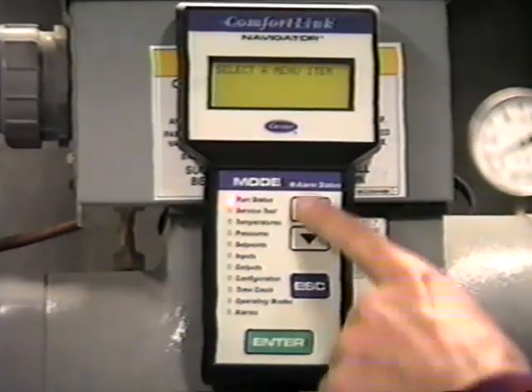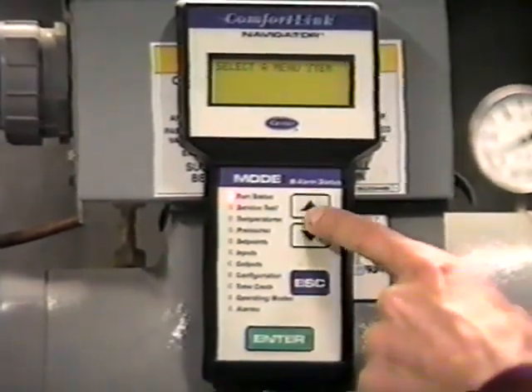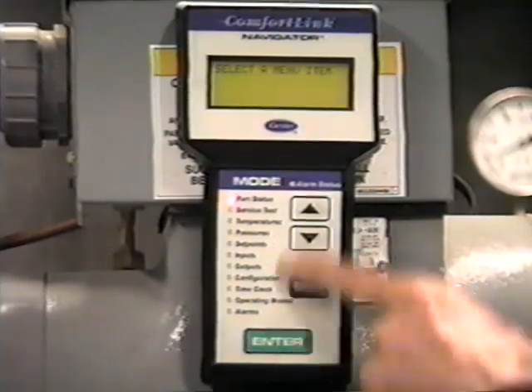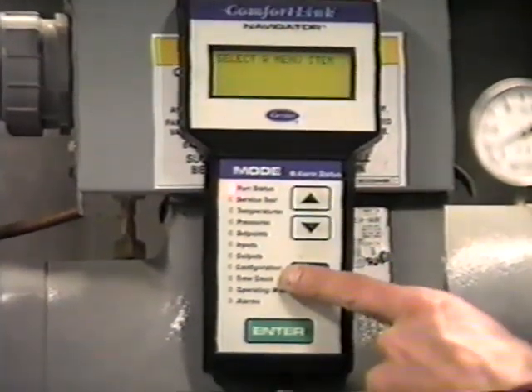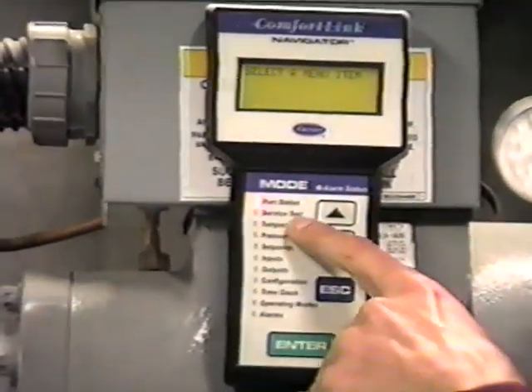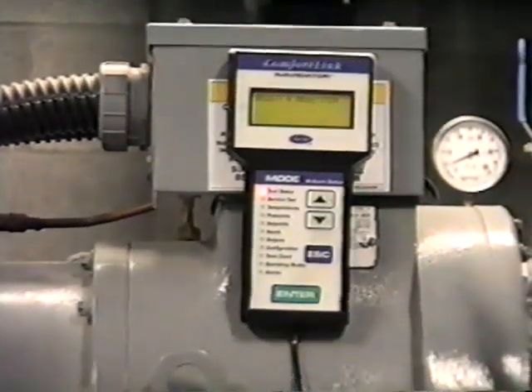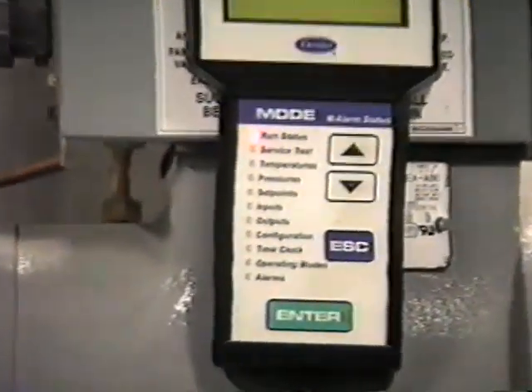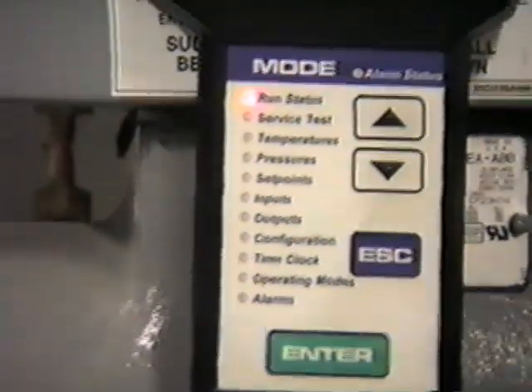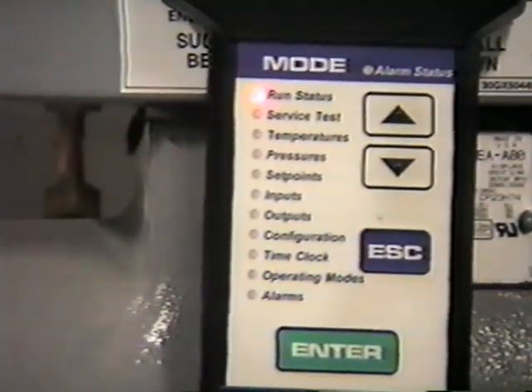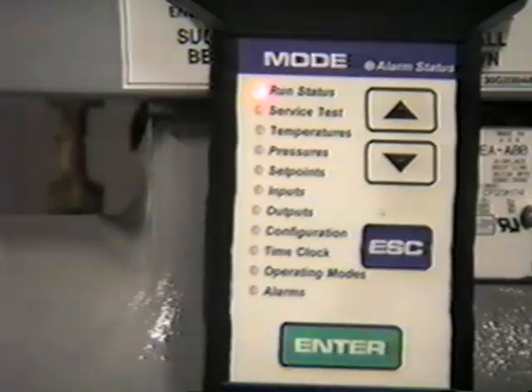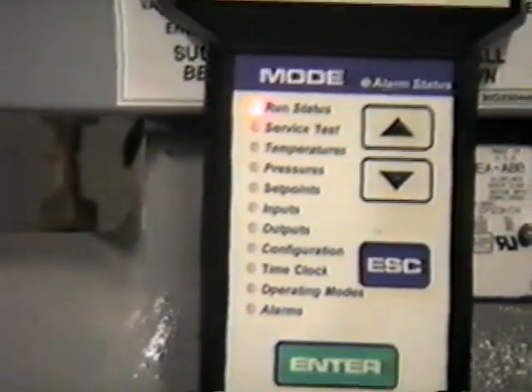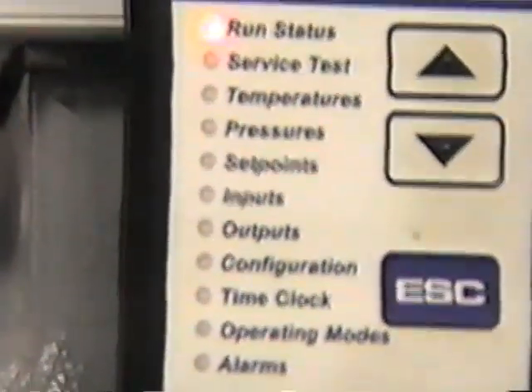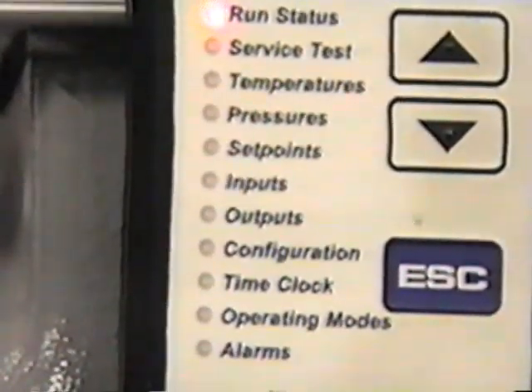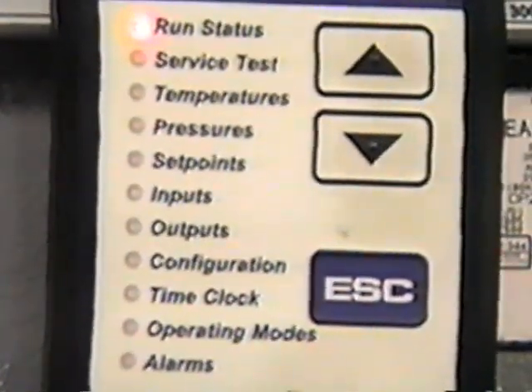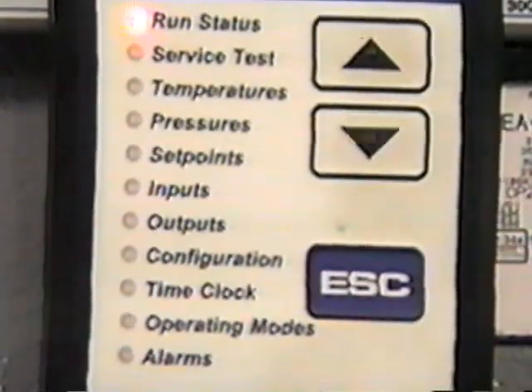At this point, we can use the up or down arrow to go to the primary mode that we want to be in. And the modes are service test. Service test is one of the functions we did at initial startup. It allows you to go in and essentially exercise all of the inputs and outputs to the controller to make sure they're functioning properly. Probably not something you'd be getting into every day. It's more of a troubleshooting procedure when you are having a specific problem.